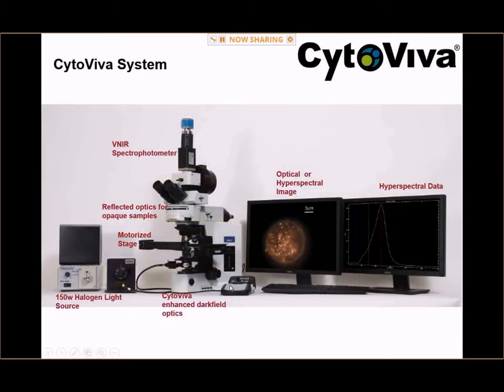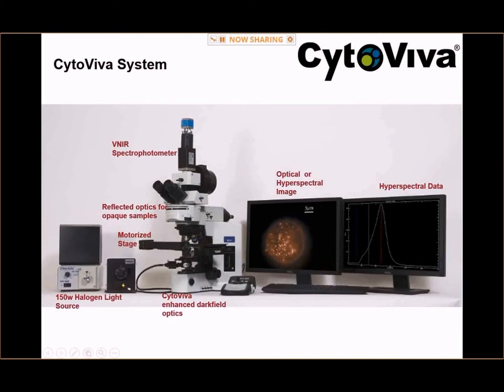We want to give you a brief overview of the footprint of the system. At the core is a standard research grade optical microscope. CytoViva's patented dark field illumination optics fit in the condenser mount of the microscope, and it's the condensing of the light that provides this enhanced dark field, very high signal-to-noise image. There's a spectrograph with an integrated detector in the C-mount of the microscope, and an automated stage that pushes the sample across the field of view to build the hyperspectral image file pixel row by pixel row. Those sample images Leslie was showing you take about two to three minutes to capture.